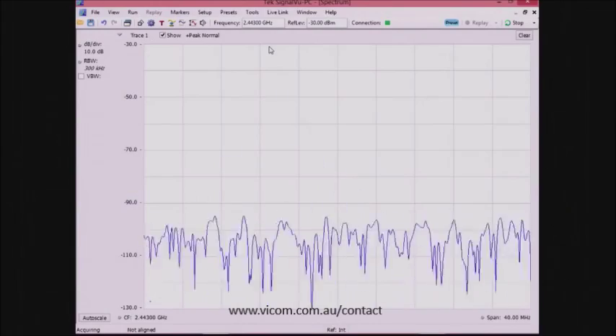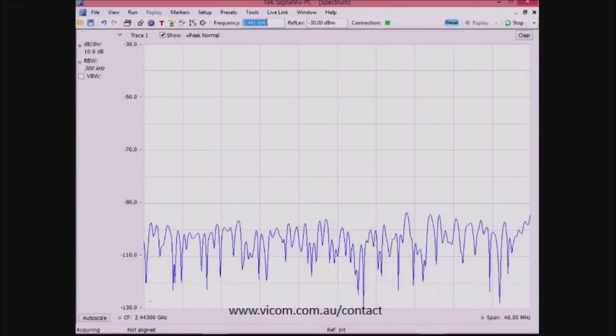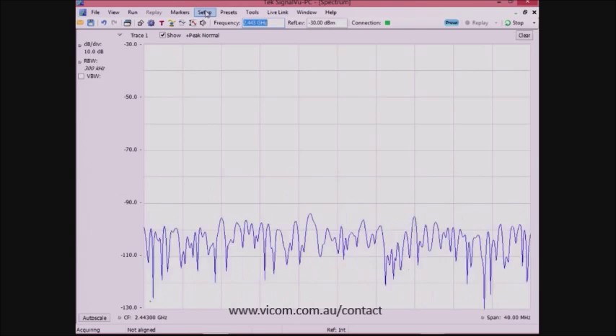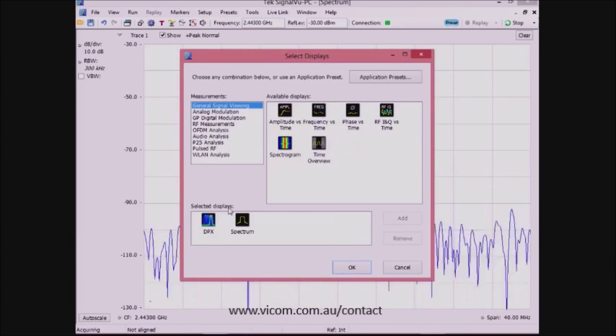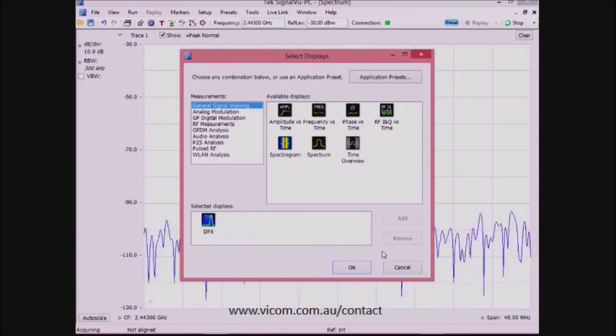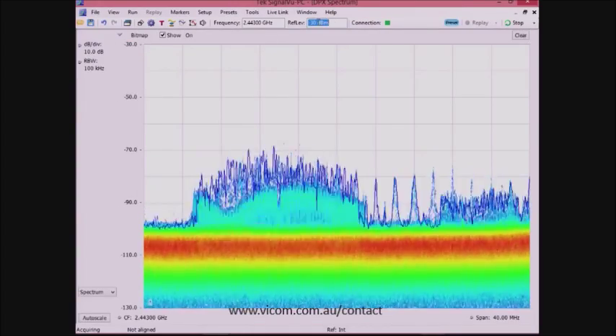We'll look at how the real-time capability in the SignalVu platform can take advantage of this instrument's 40 MHz real-time bandwidth. We start with the instrument in a preset condition, then tune to the frequency band of 2.45 GHz. Then we turn on the real-time DPX display. Next, we reduce the reference level to make sure that we can see the signal on the screen.